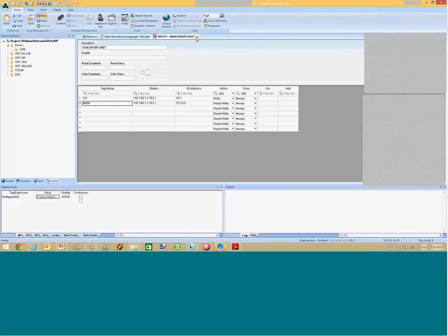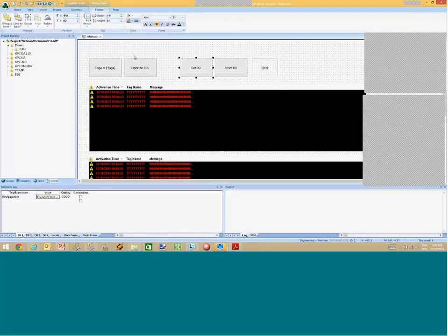So the CAN protocol is a proprietary protocol that implements all the layers of the protocol, including the proprietary layer. So in order to communicate with devices through the CAN protocol, you need a physical adapter for the CAN physical layer. And here in this combo box, there are different channels, and different adapters that we support from Hilscher, PEAK, and the TPC HMI from Advantech. So once you define your physical adapter, the driver will implement the standard CAN protocol, and the J1939, just like CANopen, are just customizations of the raw CAN protocol.